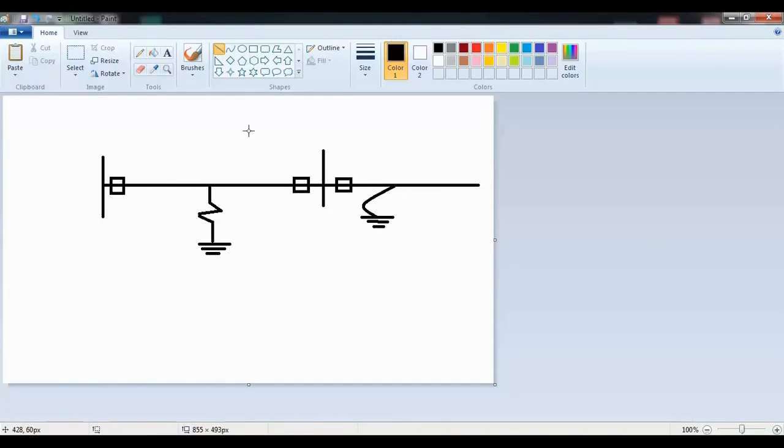But in the short lines, the understanding between the relays is done through zone 2, which is the adjustment we made to be used with short lines. So the information exchange between the relays is done with zone 2, which is originally zone 1 understanding. Is that clear? So the channel transmission depends on pickup of zone 1, pickup of zone 2, and pickup of zone 3, right?